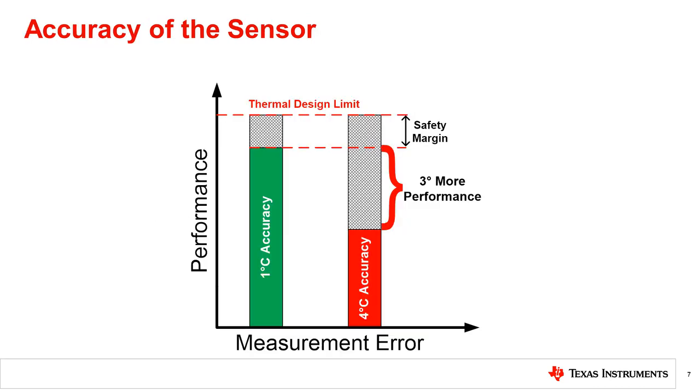Beyond response time, accuracy is another temperature monitoring and protection specification that should be considered. Accuracy will help to improve overall control systems' reliability. Any sensing type has a measurement error in degrees Celsius, which needs to be compensated from the ideal measurement. Smaller error will increase system reliability before you have to turn off the system showing an over temperature error. For a system designer, this will lead to a loss in system efficiency by power cycling or throttling processor performance before it is truly required.